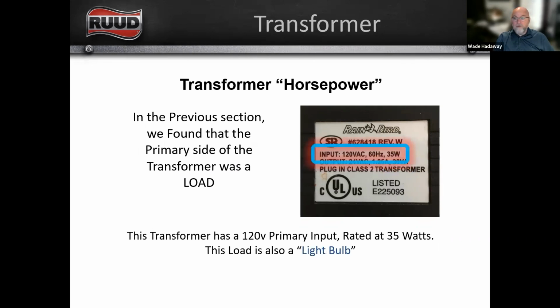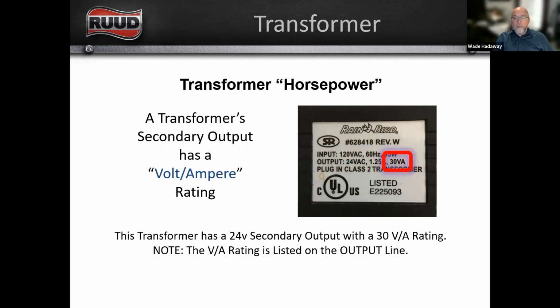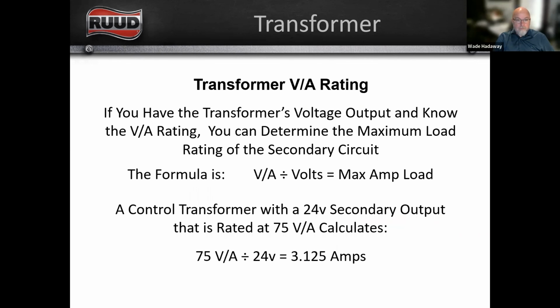You could get a 40 VA transformer, you could get a 75 VA transformer. You want to make sure that the transformer you're using is right for the application. The input side of this transformer happens to be 120 volt, 60 hertz, 35 watt, but again, our output is 30 VA. If you know the VA rating of the transformer and you know the voltage, you can calculate the maximum amperage load that transformer can handle.